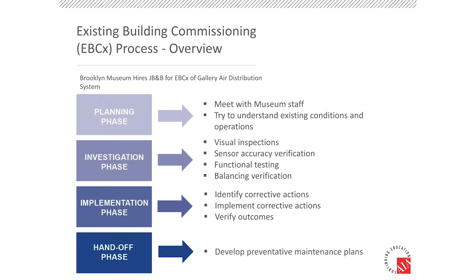And then ultimately the handoff phase, which is super critical also. The investigation and implementation phases are what people think of when talking about commissioning, but it's really the start and the finish that make or break what's going to happen going forward—we can make sure we leave it in a good place, but what happens even a year down the road? Luckily for us, we worked with the controls contractor that had a service contract with the museum, very familiar and going to be around a long time, and the operators themselves worked with us side by side to make sure any deficiencies we picked up during that phase were understood by them going forward.